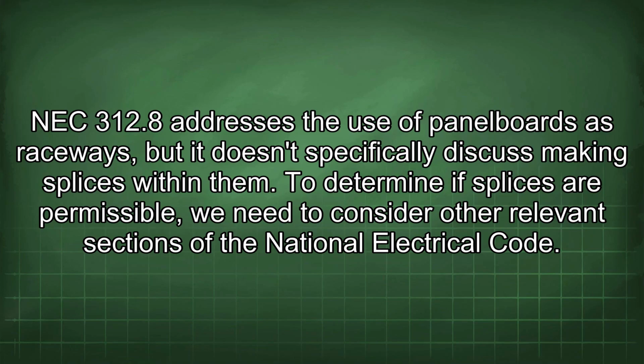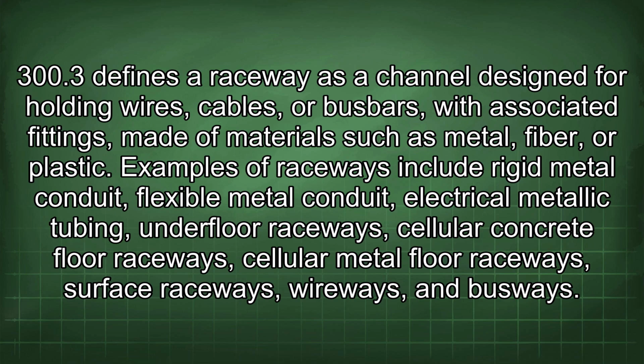NEC 312.8 addresses the use of panelboards as raceways, but it doesn't specifically discuss making splices within them. To determine if splices are permissible, we need to consider other relevant sections of the National Electrical Code.